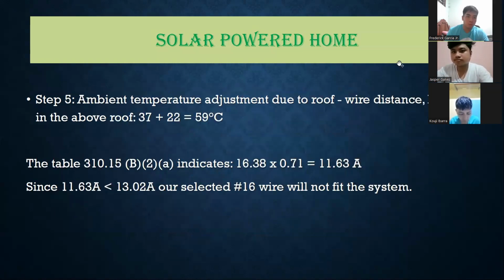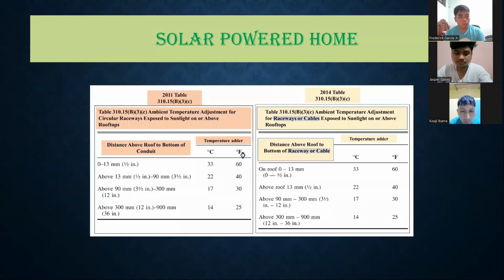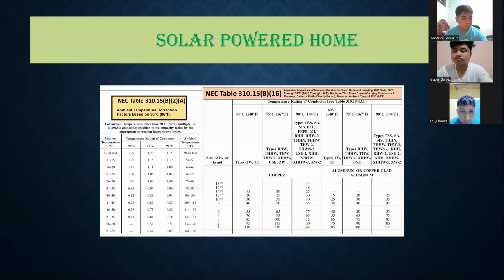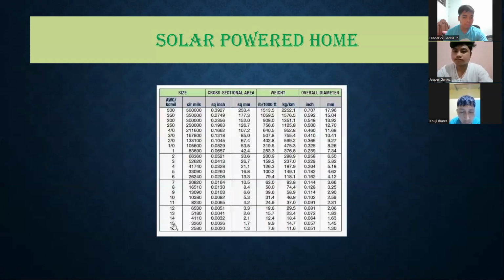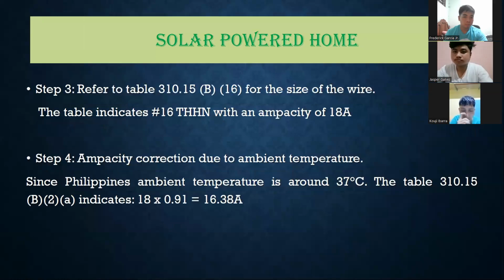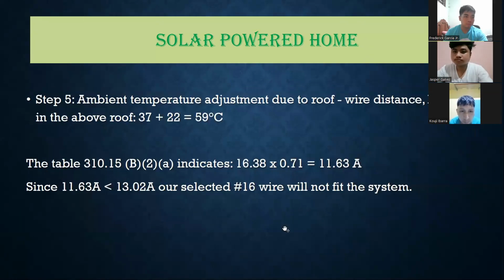Okay, so now we have the ambient temperature adjustment due to roof wire distance. For 1/2 inch above the roof, we have the ambient temperature plus 22, so we have 59 degrees Celsius. Now from the previous table again, we multiply the previous value that we got, 16.38 amps, by 0.71. We got that 0.71 from this table right here. And now we get 11.63 amps. Take note that 11.63 amps is less than our previously calculated IPV new of 13.02 amps. So our selected number 16 wire will not fit the system.